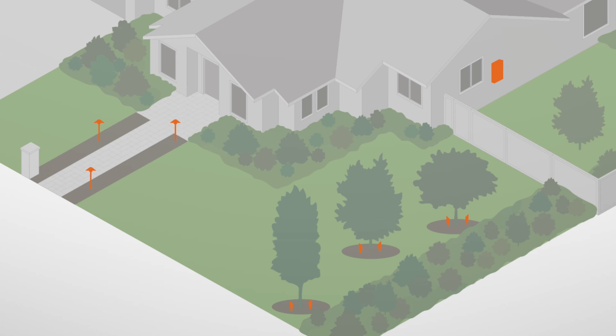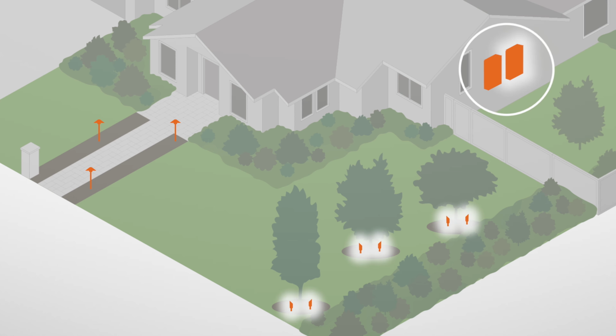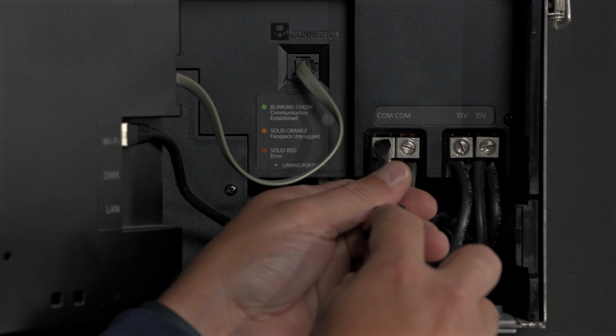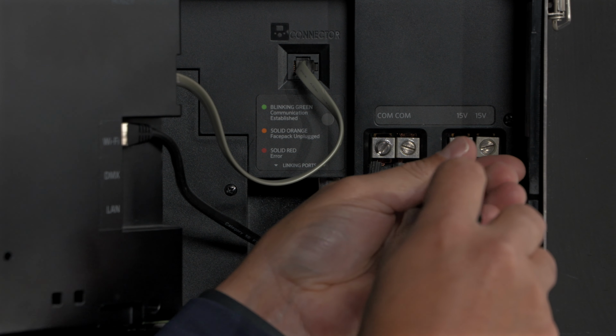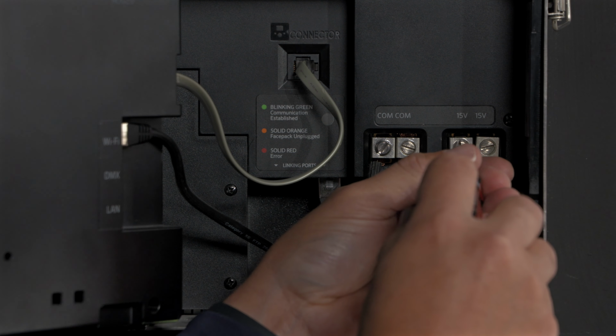In the field, remove some fixtures from the transformer that's overloading and redistribute them to an additional transformer or satellite by taking out wire runs and installing them into the other controller. Go over to the primary that is overloading, remove a wire run, and add the wire run to a new transformer. The wires are now installed.